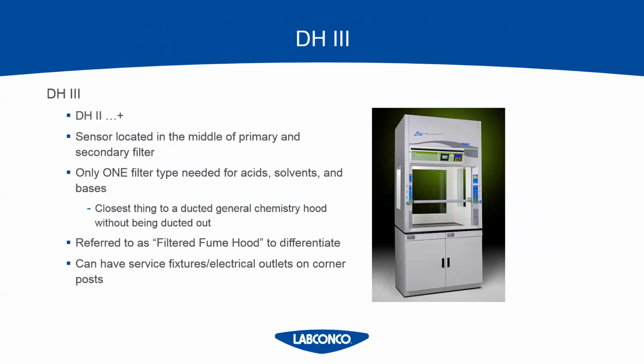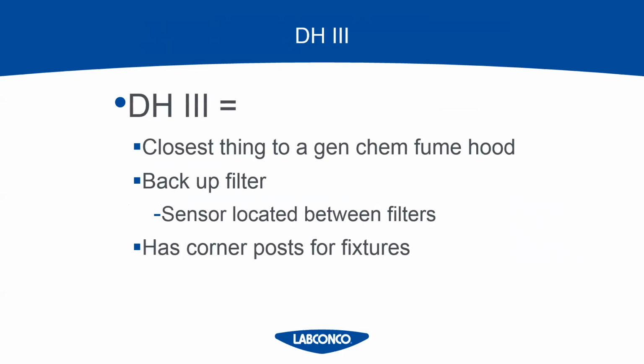So overall, these hoods are much more sophisticated, but with that sophistication comes more user responsibilities. We'll get into that in more detail. But Labconco's hoods that fall under the DH3 category are called the Echo and the Aero filtered fume hood. In a nutshell, for the DH3s, it's the closest hood to a general chemistry hood without being ducted out, since it can filter out the acids, bases, and solvents at the same time, and it can have service fixtures and electrical duplexes on the corner posts.